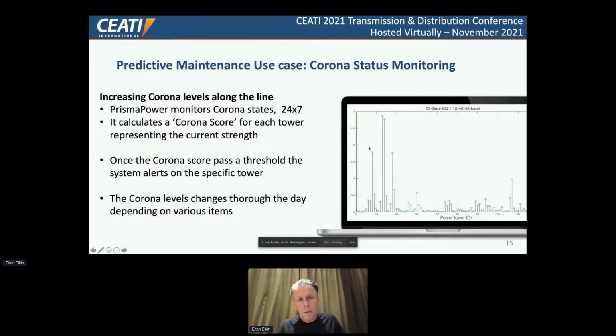Another use case is predictive maintenance, and here we're speaking about the corona or partial discharge status of the grid itself. So what we are doing is basically measuring the corona or partial discharge level on each tower, and we give each tower what we call a corona score. So this score correlates to the level of partial discharge or corona effect on the tower. And when it passes the threshold, we can give an alert indicating the towers where the corona score is higher than the required threshold.